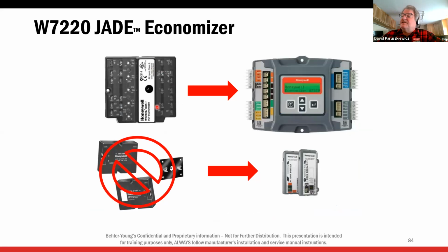All right, the 7212, which you see on the top here, this is the old economizer controller. It plugged into the motor. These are the sensors for it. First thing, these sensors are not compatible. So as they phased this 7212 out, eventually we'll be switching to the Jade. If we're switching over to the Jade, we have to switch all the sensors as well to the Jade sensors.